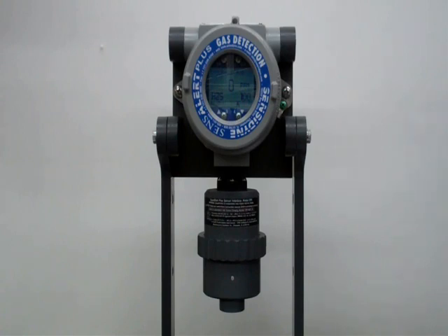This is the Sensidyne SenseAlert Plus gas detection transmitter. It has a really cool feature called Test On Demand, or TOD, that I'm going to show you today. It has a cell that actually emits the amount of gas to show that your sensor is either dead or alive.